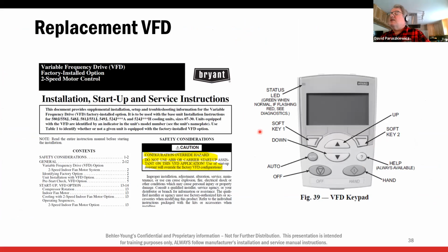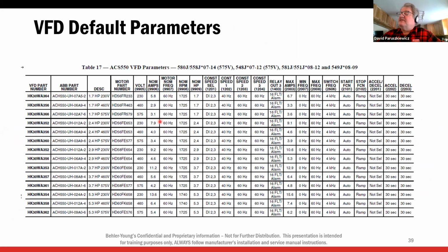All right. So the drive will also come with this book, and this is going to tell us our parameters. This is pretty straightforward. So I need the blower, motor, and drive part number. So right here is the number for the drive. You look on the drive, you look at the Bryant part number, you look at the blower motor part number, you find them on this little chart. Right across the line is my parameters.